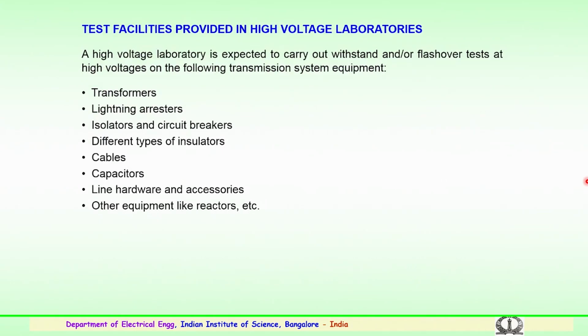So, what are the test facilities which could be provided in the high voltage laboratories for research, developmental and testing aspects? The high voltage laboratory is expected to carry out withstand tests, that is, for a duration specified by the standards, for what time the equipment could withstand the surges which it sees in field conditions, and it could be a flashover test. So, it could be a withstand test or a flashover test at appropriate high voltages, and these could be conducted on the following transmission equipment, like transformers. Transformers will be tested for AC withstand, impulse withstand, chopped wave and so on.